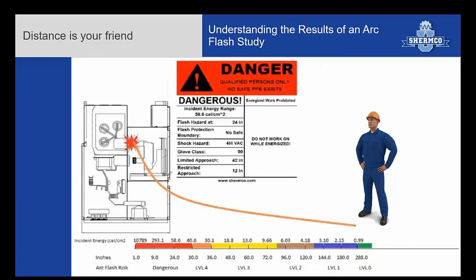So for instance here, in this example, this arc flash sticker shows the flash hazard at 24 inches. So the engineers selected 24 inches. They came up with 58.6 calories per centimeter squared. So this is a level that is dangerous. It's above 40 calories. But it's calculated at that specific point, at 24 inches.